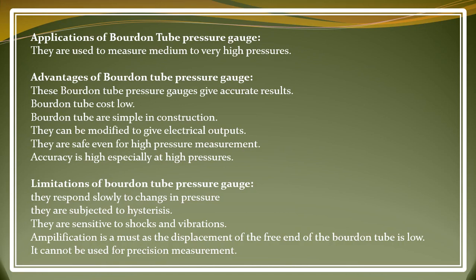They are subjected to hysteresis. As you can understand, the response in the right direction and the left direction is different because of the mechanical assembly, so it can also be subjected to hysteresis. They are sensitive to shock and vibration. As you can see, this is a mechanical assembly sensing through the pinion and sectors, and all the parts are very sensitive to vibration. If vibration happens or the pressure exerts any shock on this, it can deflect the pointer also, so it is very sensitive to shock and vibration.